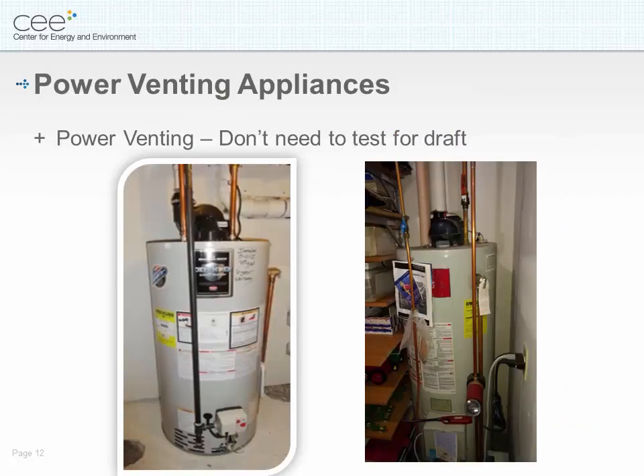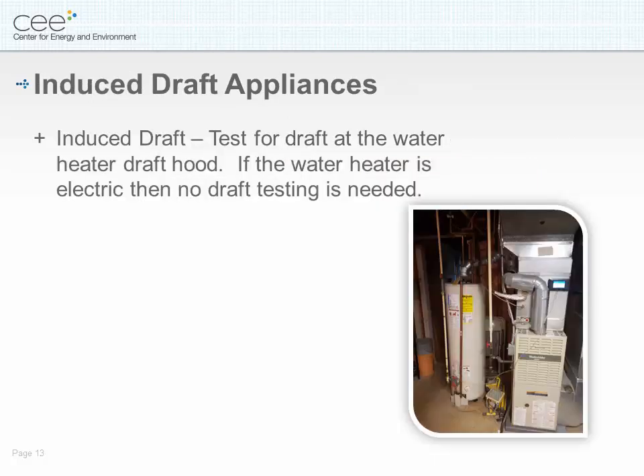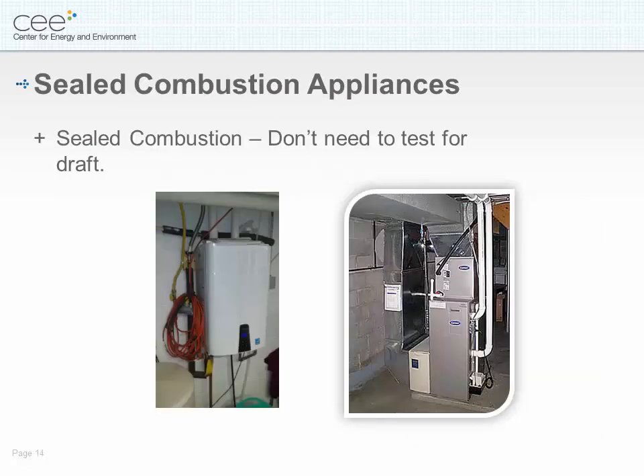Power venting appliances: you do not need to test power venting appliances for draft. Induced draft appliances: test for draft at the water heater draft hood. If the water heater is electric, then no draft testing is needed. Sealed combustion appliances: you do not need to test for draft.